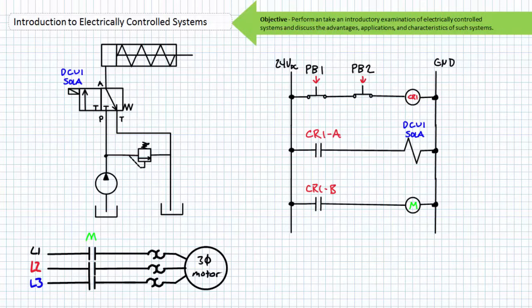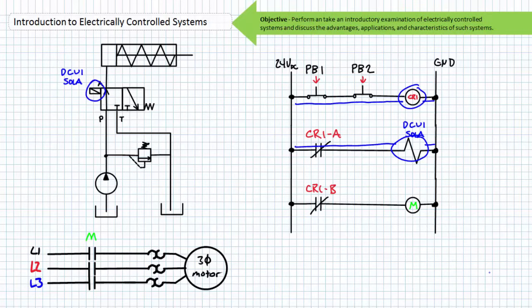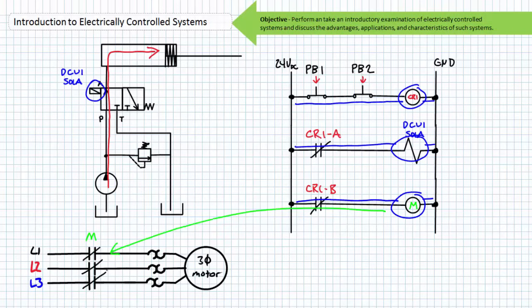If, however, an operator were to simultaneously press both push button 1 and push button 2, the coil of CR1 would be energized. When the coil of CR1 is energized, its associated contacts change states. Normally open CR1A closes, as does normally open CR1B. The now closed CR1A contact energizes DCV1 Sol A. The energized solenoid A shifts DCV1 to the straight-through position, and the cylinder extends. Simultaneously, the now closed CR1B contact energizes coil M. Coil M closes the M contactor, and the motor starts turning.